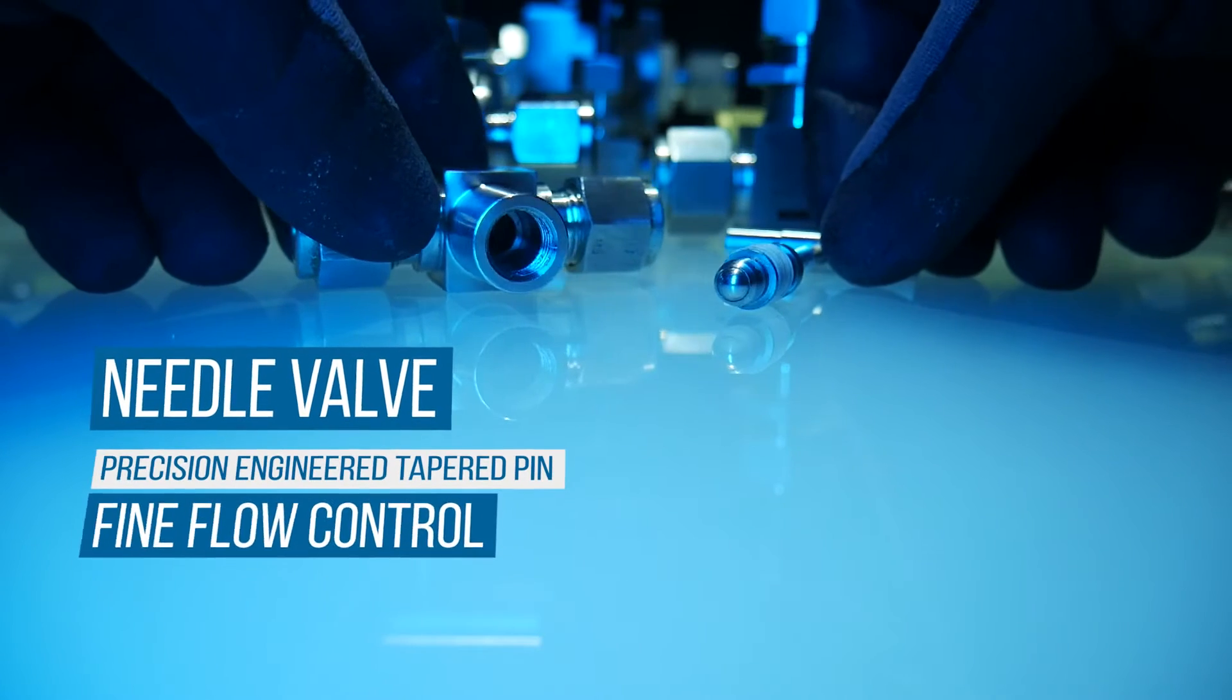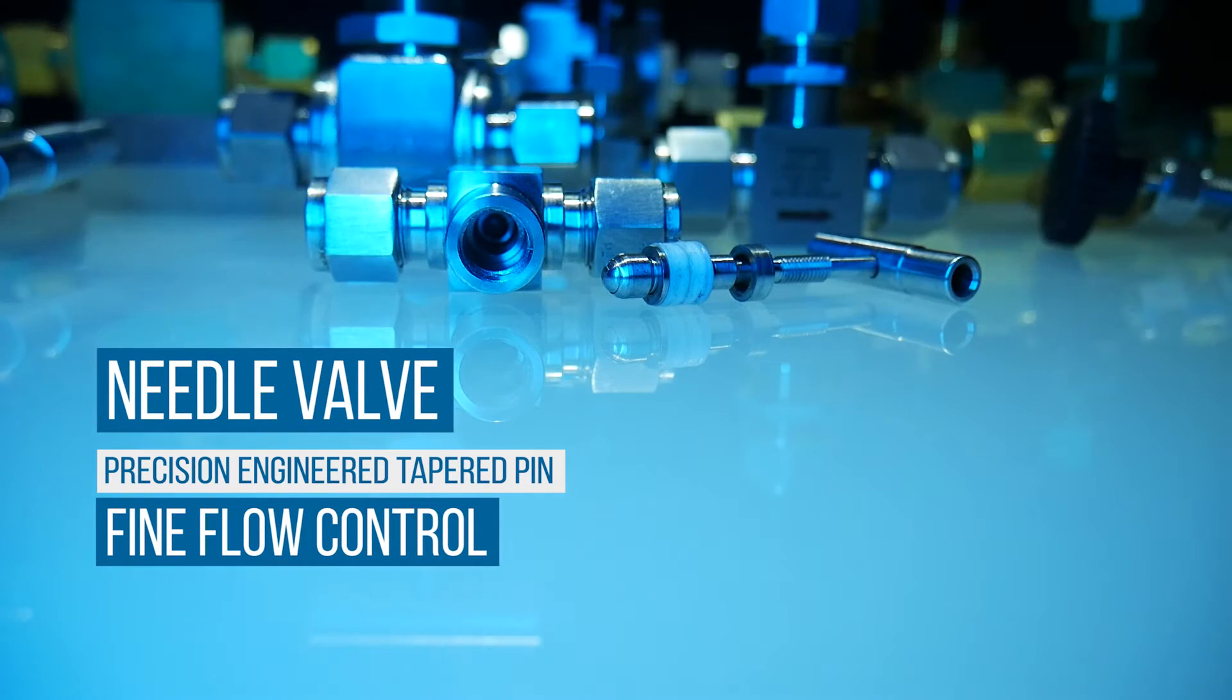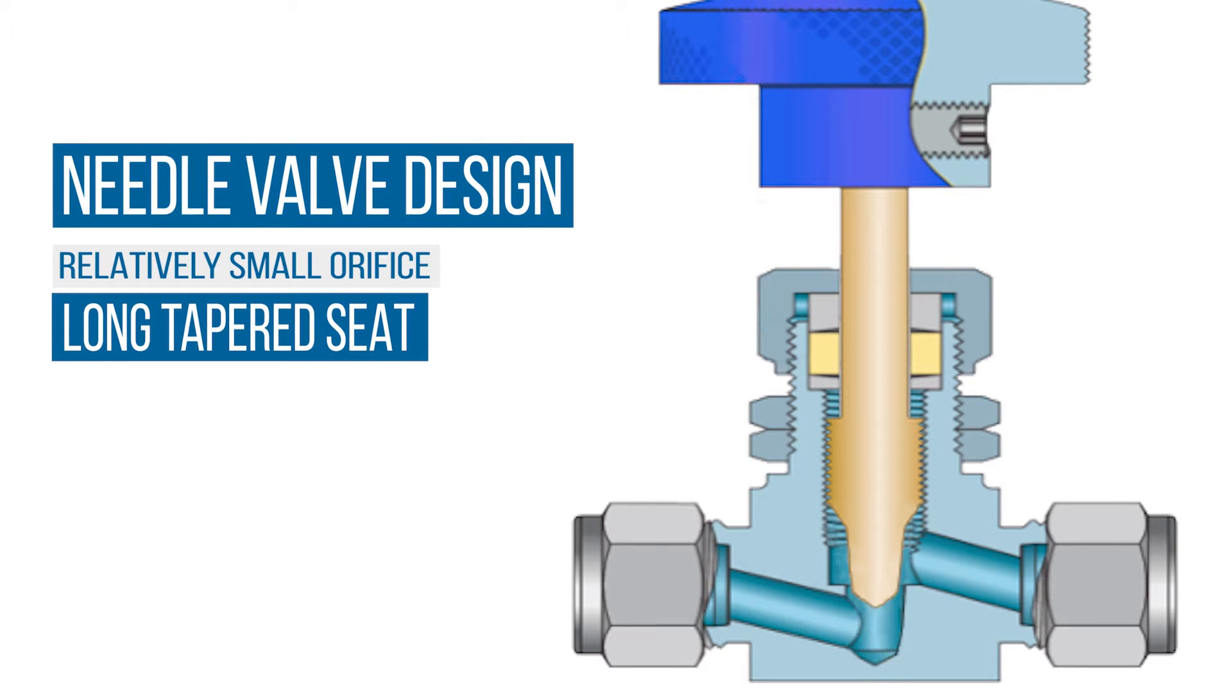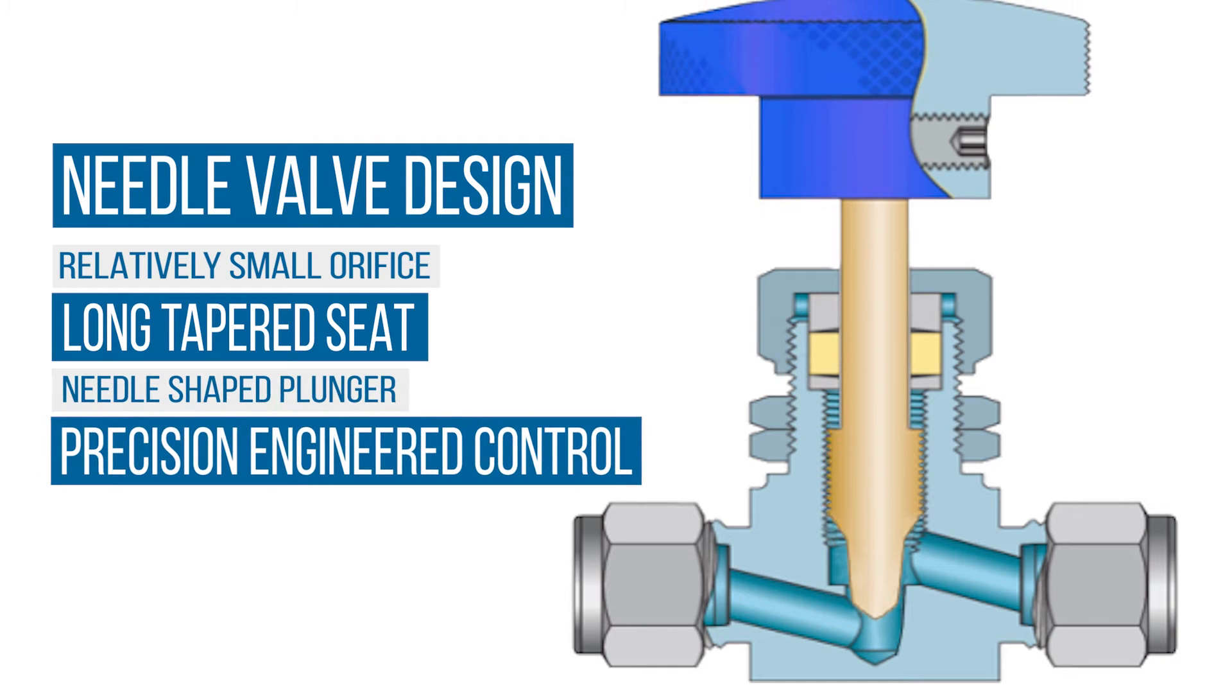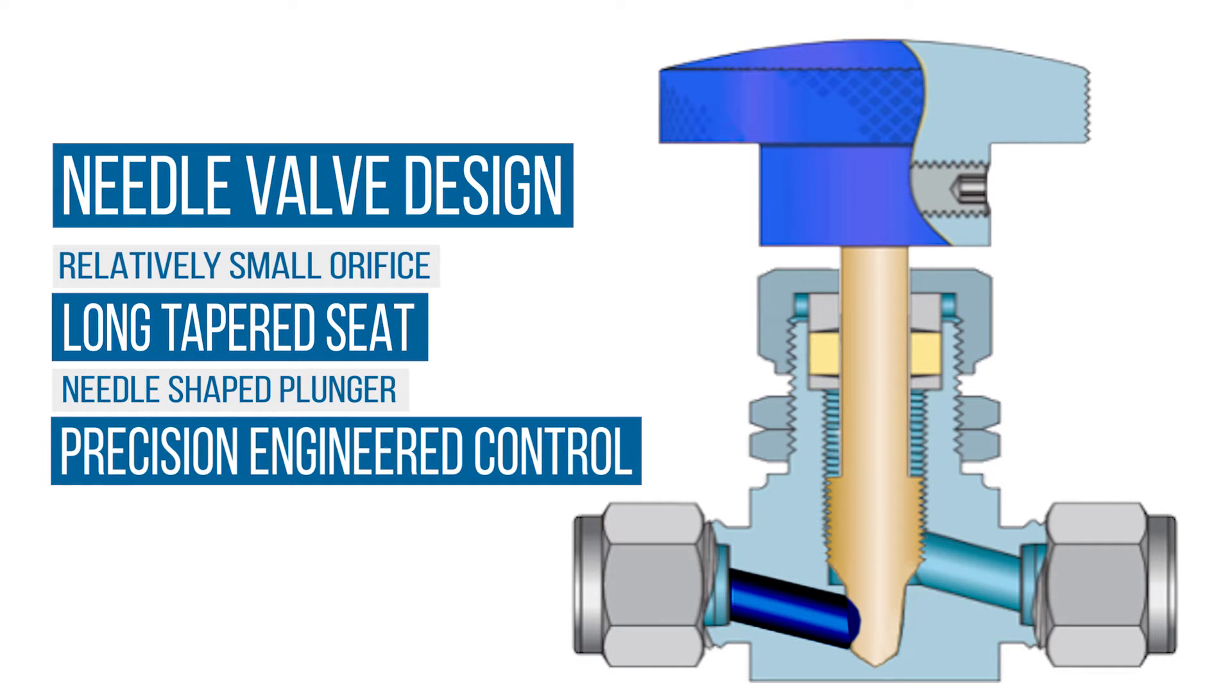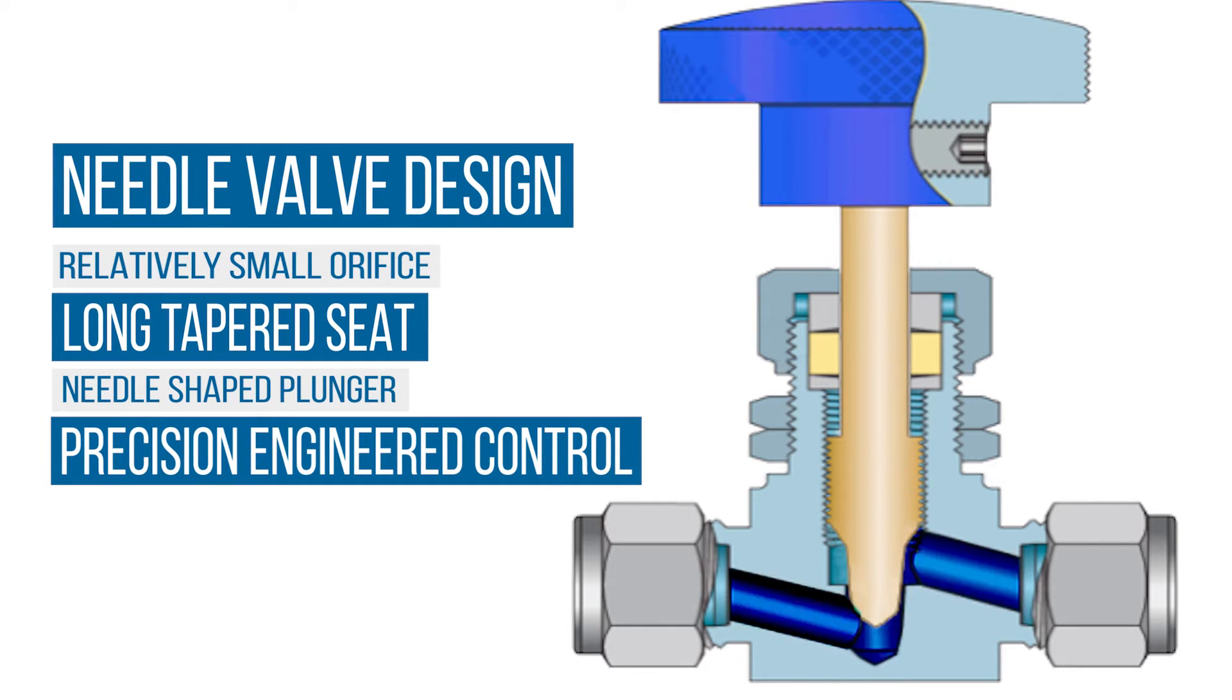A needle valve uses a precision-engineered tapered pin to gradually open the space for fine control of flow. A needle valve has a relatively small orifice with a long tapered seat and a needle-shaped plunger on the end of a screw, which precisely fits the seat for the valve shutoff. When the needle valve screw is turned, the plunger retracts allowing flow between the seat and the plunger.